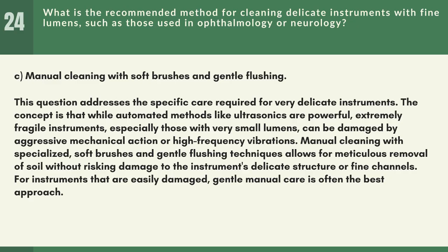This question addresses the specific care required for very delicate instruments. The concept is that while automated methods like ultrasonics are powerful, extremely fragile instruments, especially those with very small lumens, can be damaged by aggressive mechanical action or high-frequency vibrations. Manual cleaning with specialized, soft brushes and gentle flushing techniques allows for meticulous removal of soil without risking damage to the instrument's delicate structure or fine channels. For instruments that are easily damaged, gentle manual care is often the best approach.